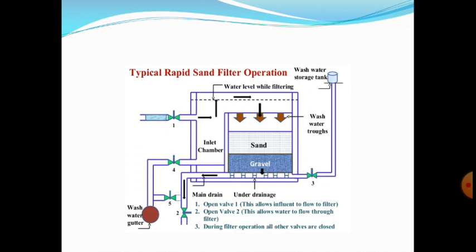This is the example of a rapid sand filter. Water is allowed in from valve 1, which allows influent to flow to the filter. Opening valve 2 allows water to flow through the filter. During filter operation, all other valves are closed. The influent enters the filter and passes through sand and gravel layers, where impurities are removed. The filtered water is then allowed out from the filter outlet.